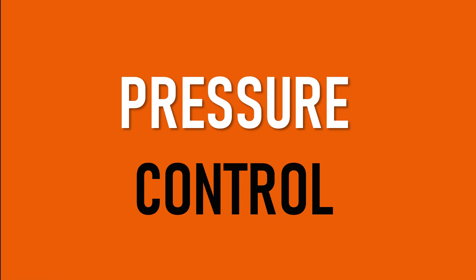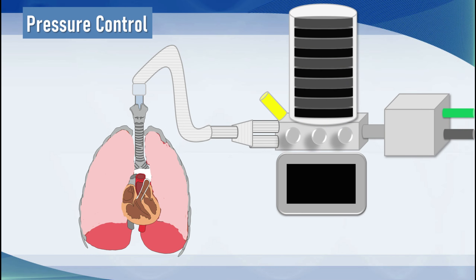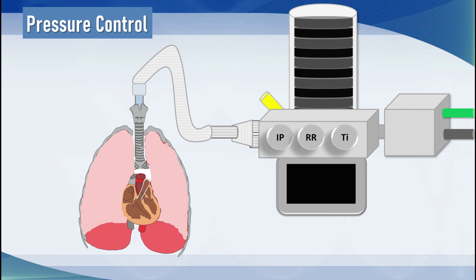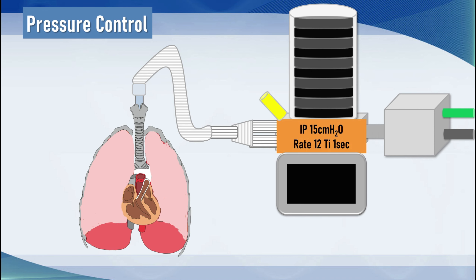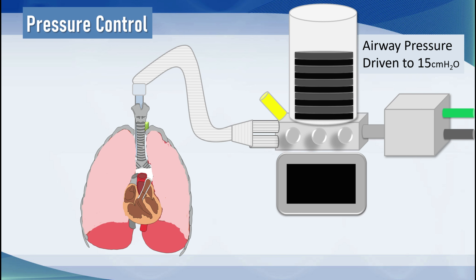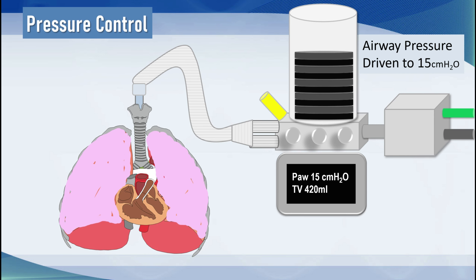Now let's move on to pressure control. In pressure control, we set an inspiratory pressure — that's our target pressure at end inspiration — which is the driving pressure above baseline, for example above PEEP or atmospheric pressure. We also set a respiratory rate and an inspiratory time so the ventilator knows when to cycle to exhalation. In this case I've set an inspiratory pressure of 15 centimetres of water, a rate of 12, and an inspiratory time of one second. The ventilator generates a flow of gas up to an airway pressure of 15 and holds that for one second, achieving an exhaled tidal volume of 420 mils.